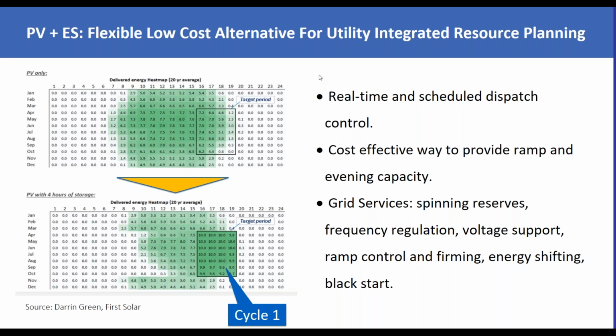This is the typical output of a one-axis tracking solar system throughout the day. Production starts around 9 a.m. and tails off in the afternoon. Look at the duck curve in California, or any major utility's load profile, and most utilities peak in the morning around 8 to 10 a.m. and again in the afternoon from 4:30 to 8 p.m. So you have this issue with solar where you've got excellent low-cost kilowatt hours, but they're delivered in the middle of the day, which as solar penetration increases can require curtailment or shutdown of other thermal assets. Shifting that energy to the afternoon using the first cycle is a cost-effective way to provide ramp and evening capacity.